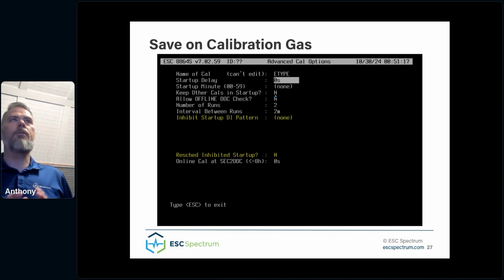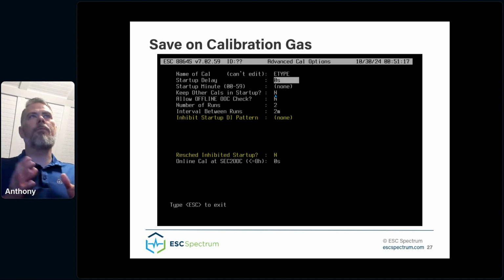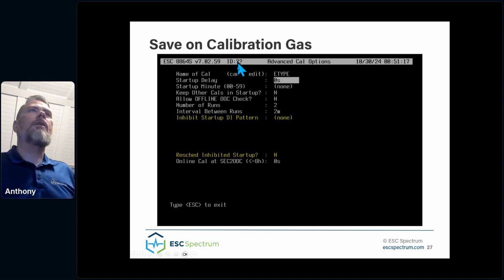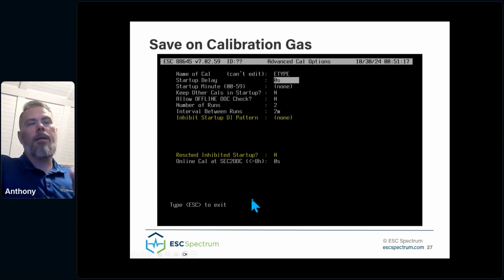You also have the ability to allow that startup calibration to be rescheduled or not, based on the reschedule inhibited startup setting. So if that's set to yes, an inhibited calibration will continue to reschedule for an hour later, for the duration of the grace period.